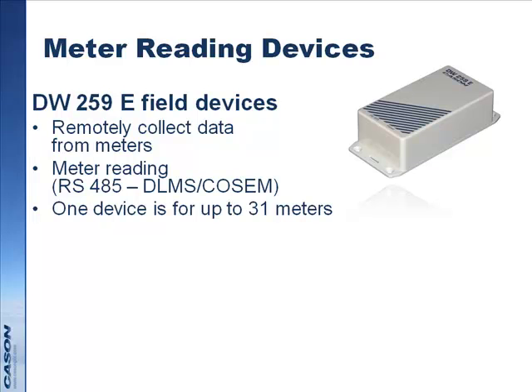It can connect to up to 16 meters at the same time, either single phase or three phase. 31 is the theoretical maximum, because altogether on a Modbus, theoretically 31 is the possible number of connectable meters, but we usually limit it to 16 because of communication quality.